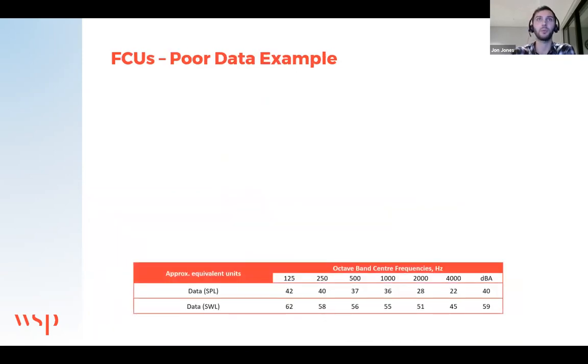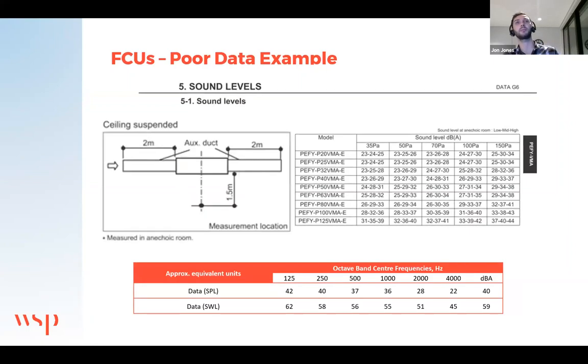However, what we also get is this type of data, where diagrammatically you have a unit with 2 meters of duct installed on either end. This is the measurement location, 1.5 meters below it. And you get, as shown here, different units, different duties, but basically a single number, which consists of a contribution from noise out of each duct, but only to 2 meters length, and noise radiated from the casing at the same time.